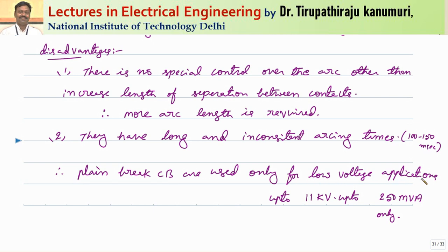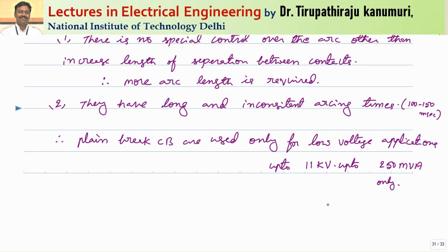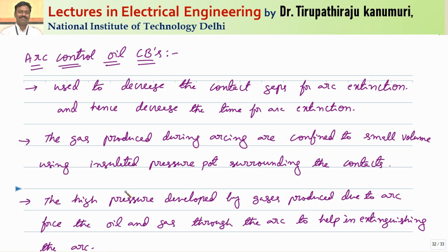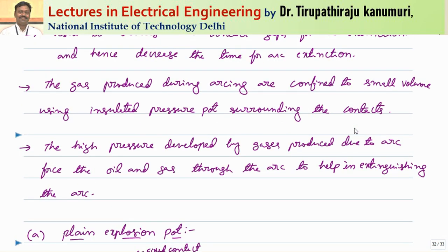Plain break circuit breakers are used only for low voltage applications — up to 11 kV and up to a rating of only 250 MVA — because as fault current or voltage increases, more contact separation is required. That is why this type is used only for low rating and low voltage applications. To increase the rating or decrease the size of the bulk oil circuit breaker, the concept of the arc control oil circuit breaker was developed. Here the moving contact is kept in a chamber — an insulated pressure pot — instead of being left directly in the open oil, to decrease the contact gap required for arc extinction and hence decrease arcing time.